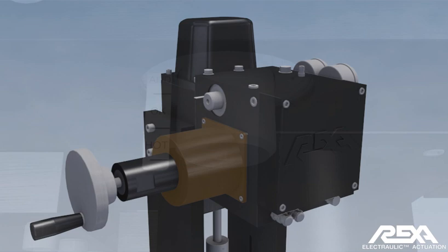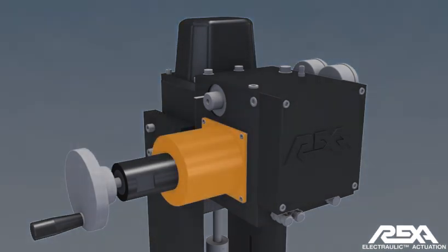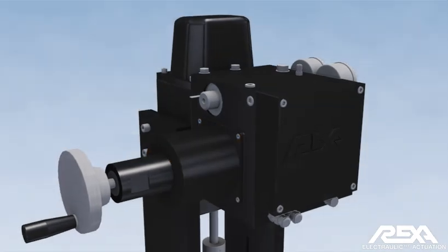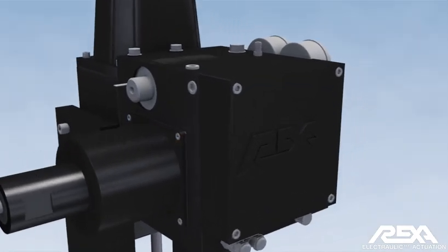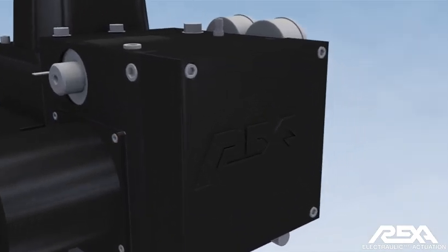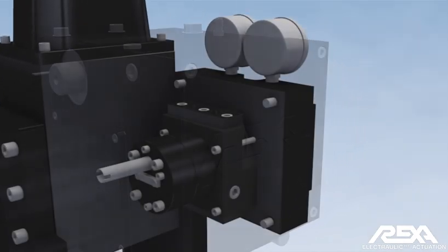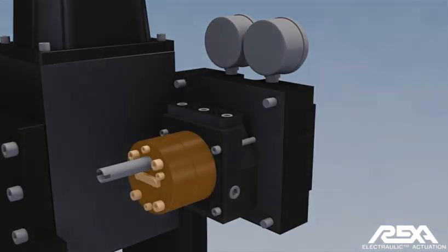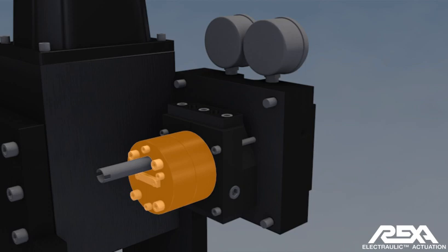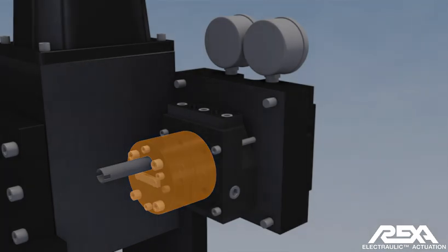The motor is a 100% duty cycle reversible unit, which drives the internal hydraulic pump. The motor is either a stepper motor or servo motor. These motors are used because their speed and direction can be precisely adjusted by the control module to meet the performance required. The motor only activates when a valve position change is required, making it highly efficient. The hydraulic pump only generates the pressure required to overcome the load that the actuator is driving, making it even more efficient.